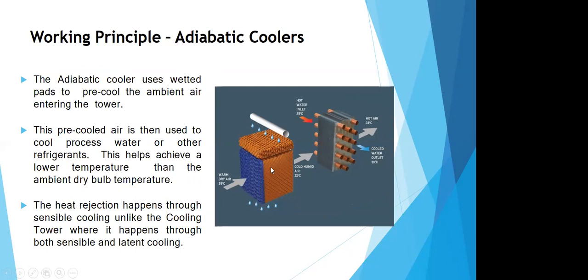So there are these CELdek evaporative pads which cool the incoming dry air, and they cool it to almost 90% of the difference between the dry bulb and the wet bulb temperature of that particular place. So you can get extremely cool air, as close to the wet bulb temperature, and that cool air in turn cools the fluid within the coils. So this helps to achieve a lower temperature than the ambient dry bulb temperature. We all know that. And the heat rejection happening in the case of an adiabatic cooler is purely sensible. There is no latent cooling involved. Unlike a cooling tower, where the majority of the cooling happens through evaporative cooling, which is latent cooling, and a part of it happens through sensible. While in adiabatic cooling, 100% of the cooling is happening through sensible cooling.